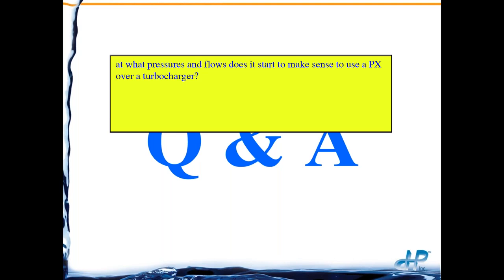At what pressures and flows does it make sense to use a PX over a turbocharger? The choice between PX and turbo isn't really a flow and pressure question — it's more a cost-of-power question. Since ERI manufactures both, if you send plant conditions to your salesperson and ask to compare the two, they'll provide what the PX will do and what the turbo will do. There's no specific pressure or flow threshold that makes the big difference. In theory the PX has infinite capacity since you can keep adding units, while the largest turbocharger ever built handles 9,000 GPM — so very large systems would be limited by turbocharger casing size.